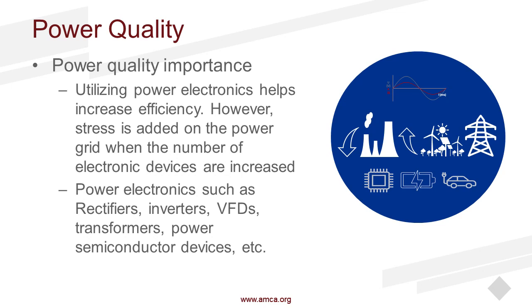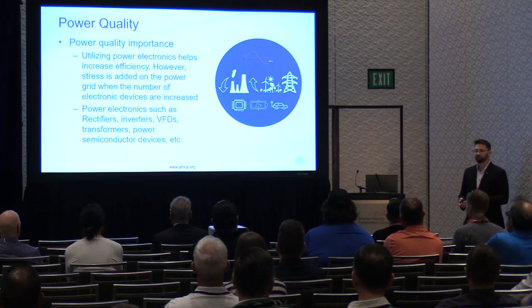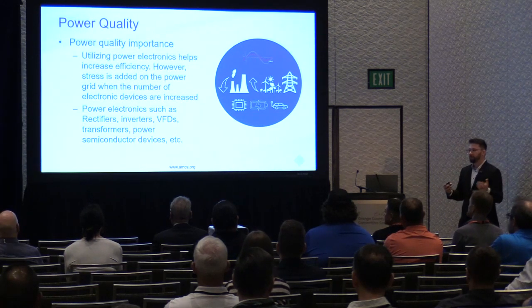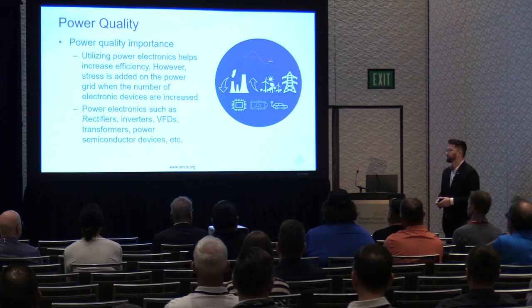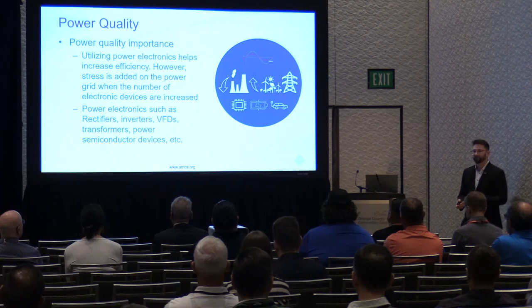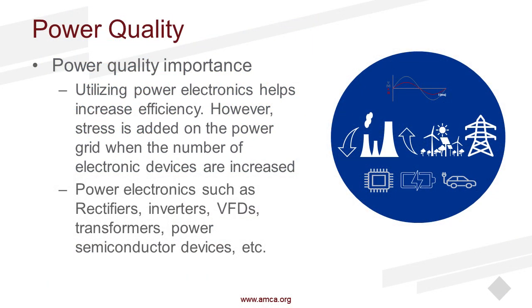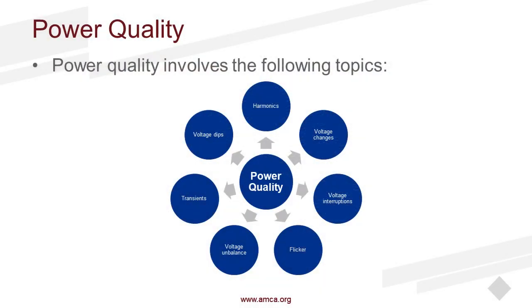So what is the importance of power quality? A lot of times we're utilizing power electronics. These power electronics are what's helping to increase efficiency within your power grid and your system. But when you add those, you're adding stress to your grid and your system. So power electronics are rectifiers, inverters, VFDs, transformers, power semiconductors, etc. These are devices that are manipulating, changing, and controlling your power, your voltage. And with that, that's where the stress comes. So power quality has a lot of different topics: voltage dips, transients, unbalance, flicker, interruptions, different changes, and harmonics, which we'll get into a little bit later.